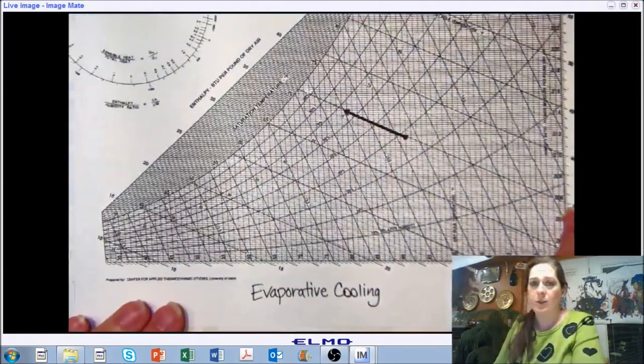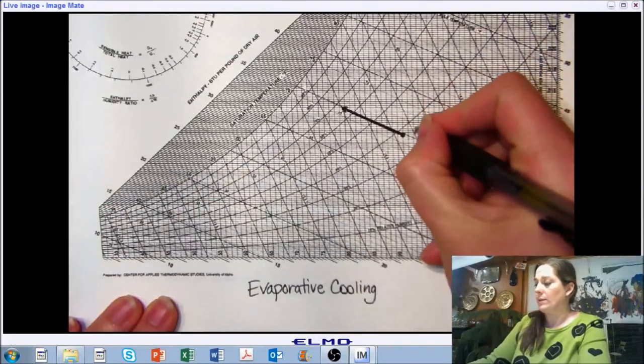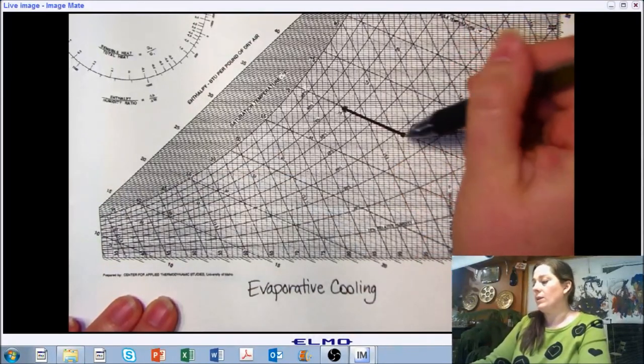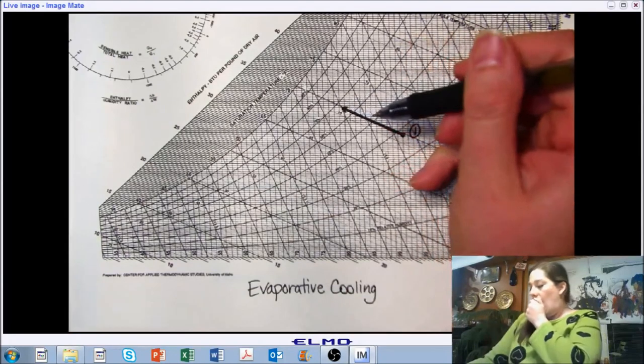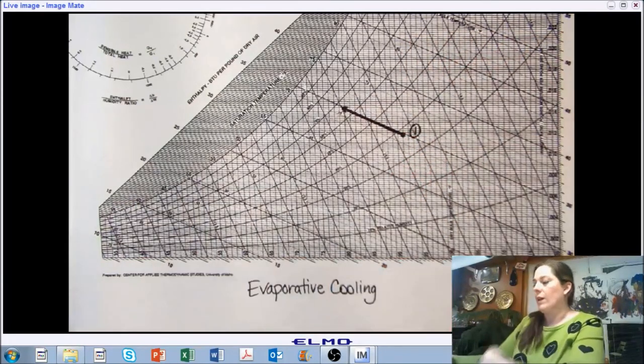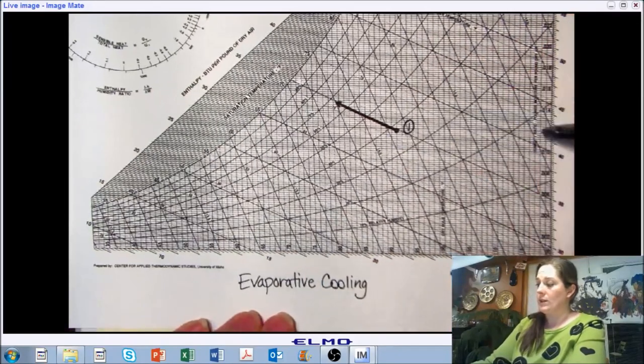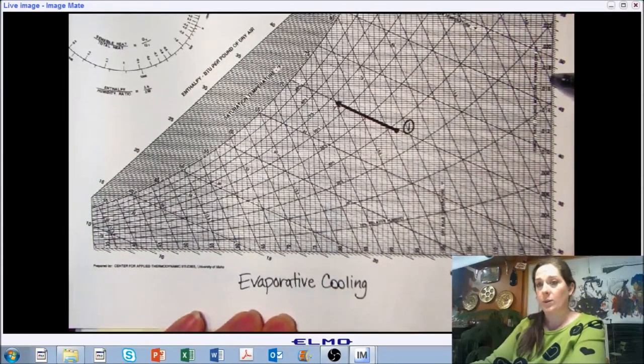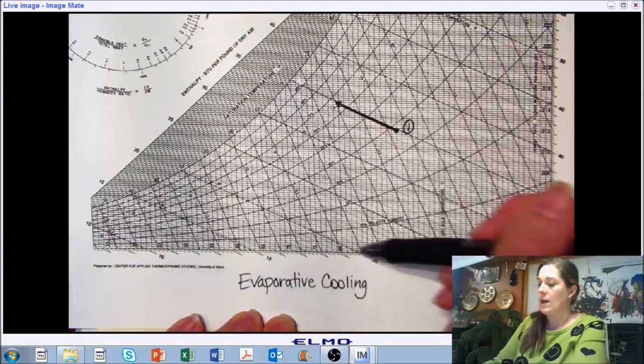All right, and on our psychrometric chart, we start with some state point and we move along the line of constant enthalpy. Along that process, we are, as you can see, adding moisture to the air, so we're moving up in humidity ratio, but we are cooling, so we're moving down in temperature.